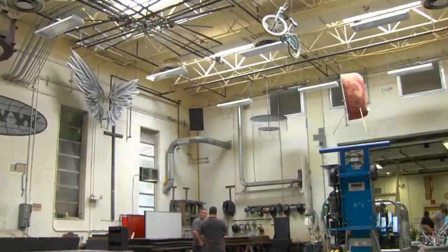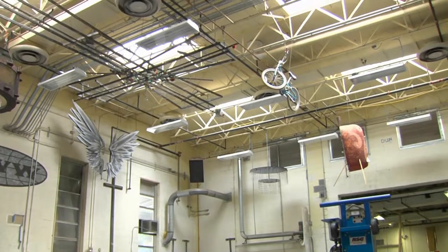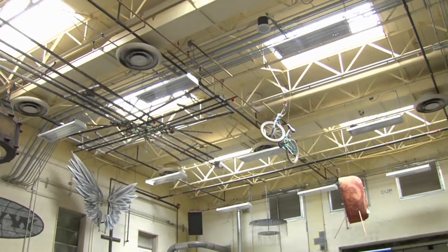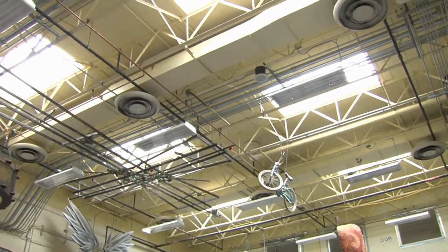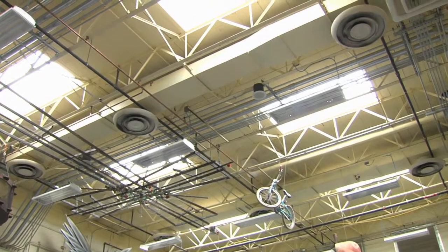And you have some daylighting opportunities in this space right here. Right now the lights are off, but we've got over 120, 150 foot candles of light. You've got compressed air that can be manually valved out, and we would recommend that the occupants valve out the compressed air when they're not using them.